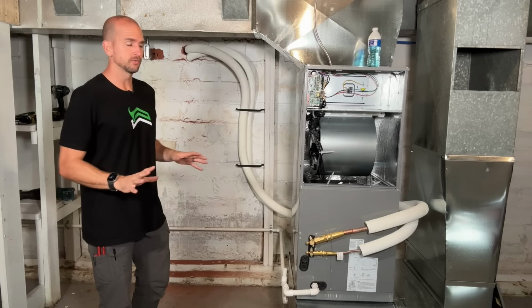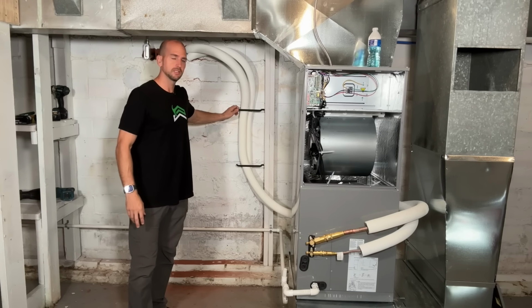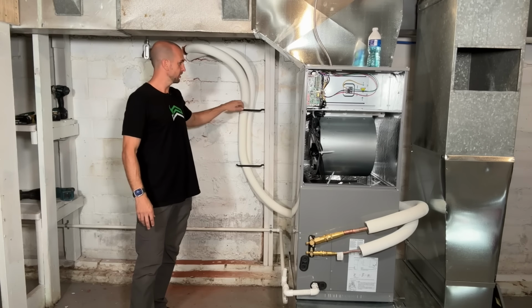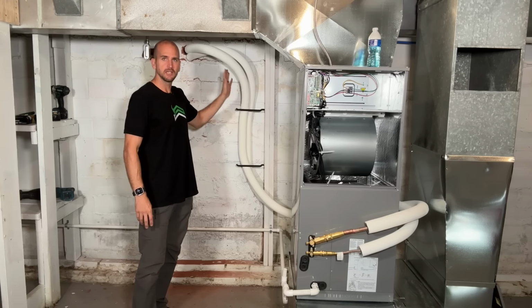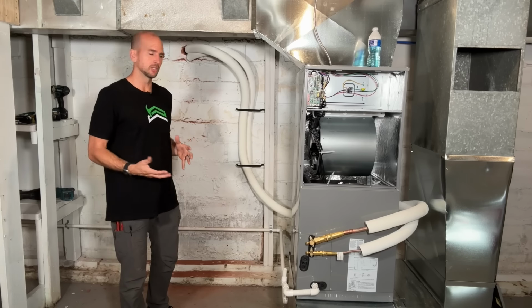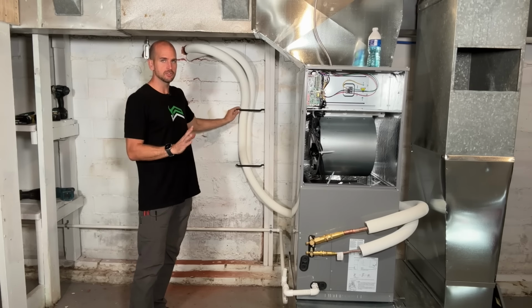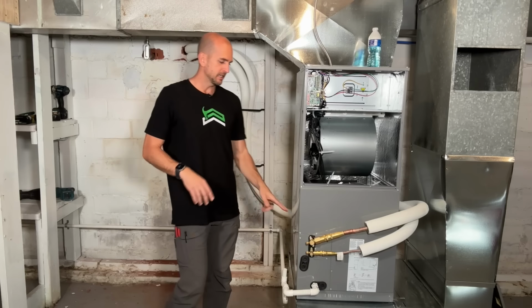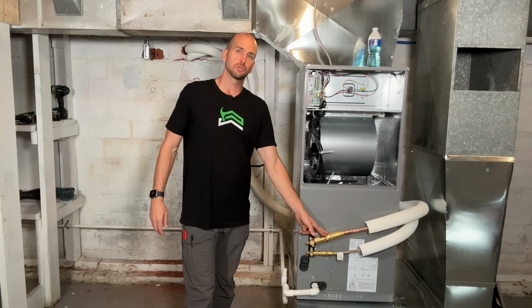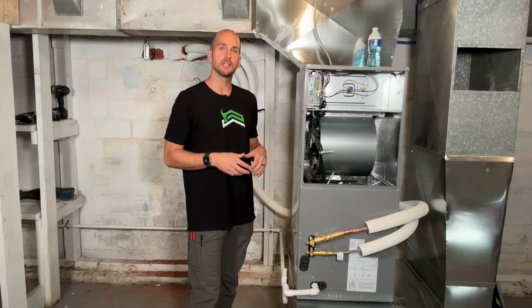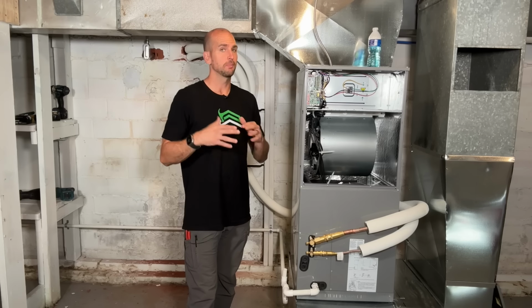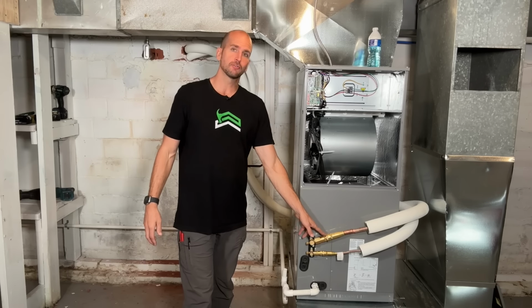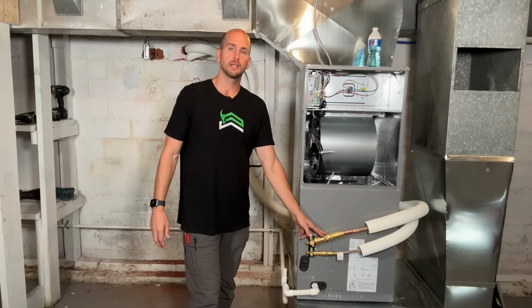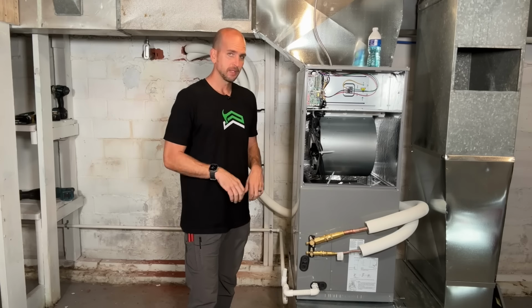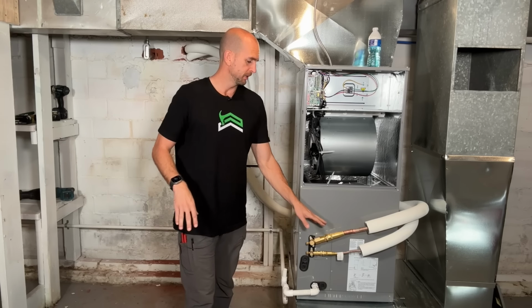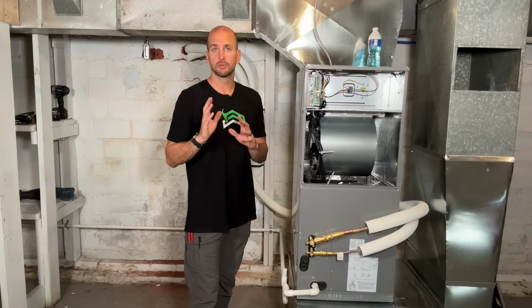So now our lines are fully installed. I did put two storage hooks here off some 2x4s just to help with my routing to keep it a little cleaner, but you don't obviously have to do that. And then also, I just tightened down my actual connections. I didn't have an open end for my torque wrench. So no, the best practice would be to tighten these down to 45 Newton meters for both of them, or 33 foot-pounds of torque. I just tightened them by hand, but we'll also on this step check for leaks.